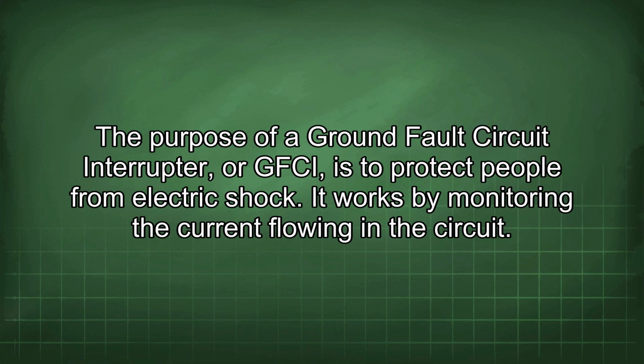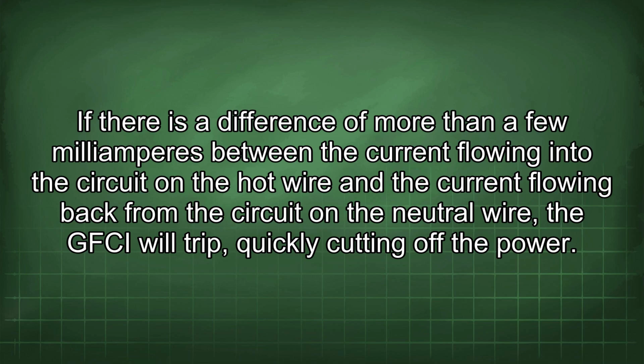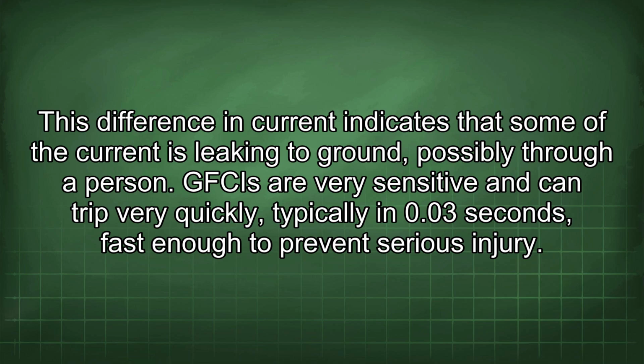It works by monitoring the current flowing in the circuit. If there is a difference of more than a few milliamperes between the current flowing into the circuit on the hot wire and the current flowing back from the circuit on the neutral wire, the GFCI will trip, quickly cutting off the power. This difference in current indicates that some of the current is leaking to ground, possibly through a person. GFCIs are very sensitive and can trip very quickly, typically in 0.03 seconds, fast enough to prevent serious injury.